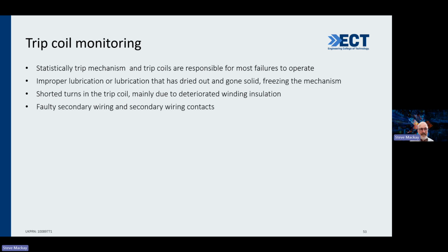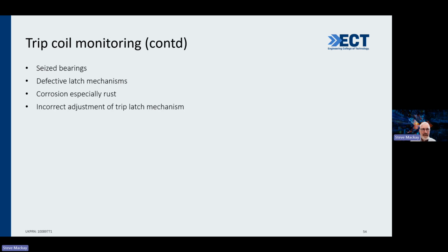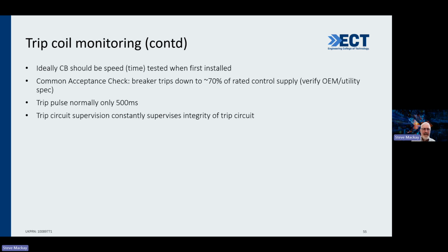Improper lubrication, or worse, the lubrication's dried out. I can never believe that oil could actually dry out. I mean, solid. Shorted turns in the trip coil, the winding insulation's gone, faulty secondary wiring. These are all things you've got to look out for. Seized bearings, defective latch mechanisms, corrosion, rust, and obviously incorrect adjustment of the trip latch mechanism. Someone hasn't done their job.